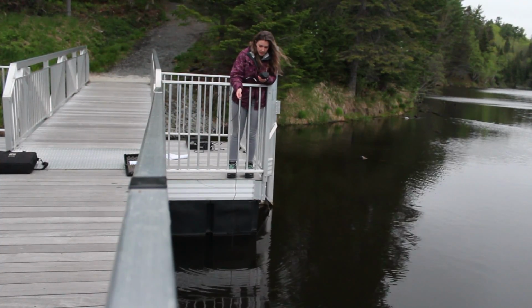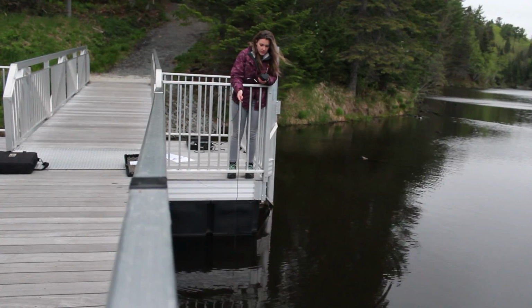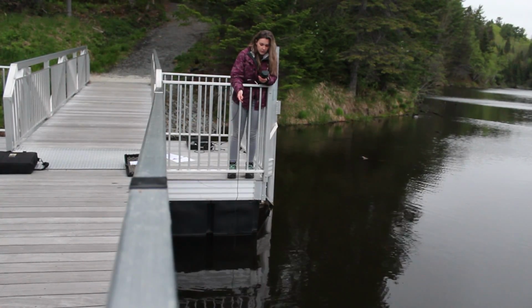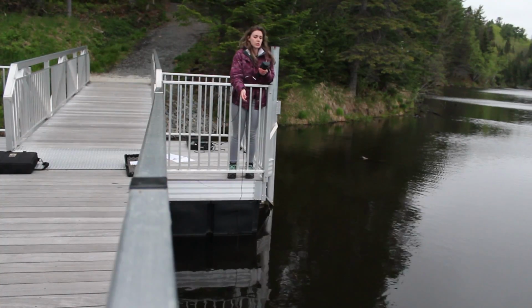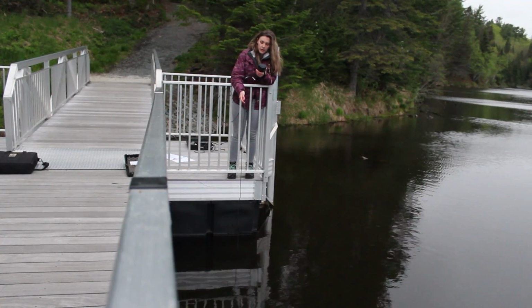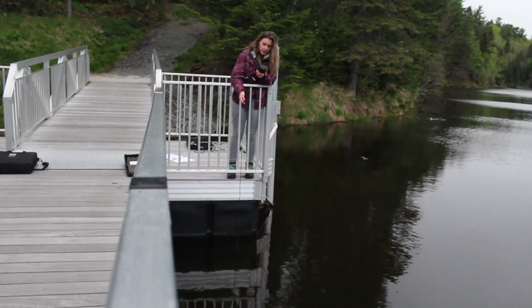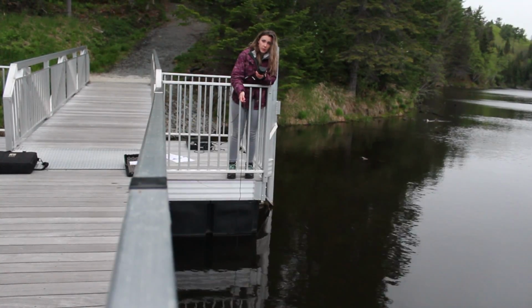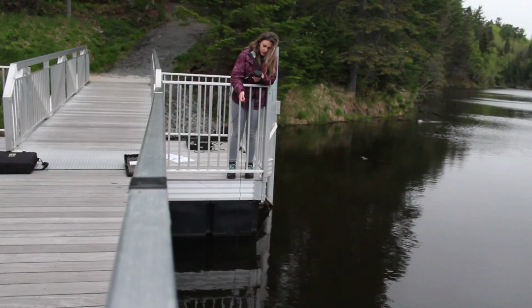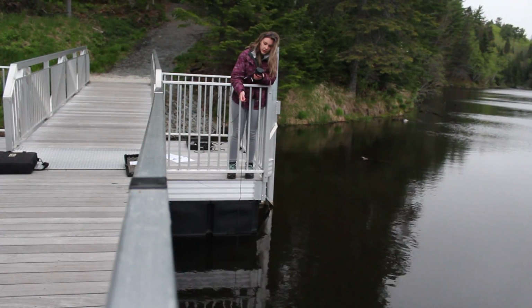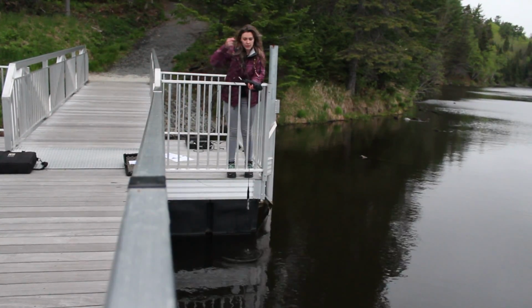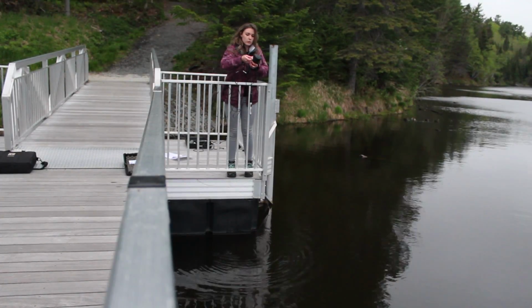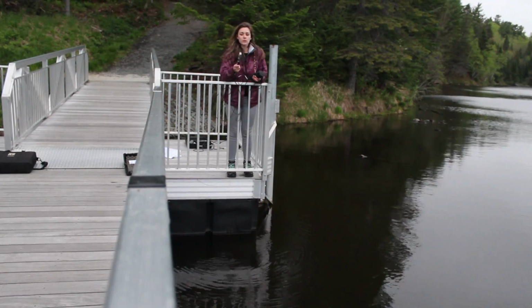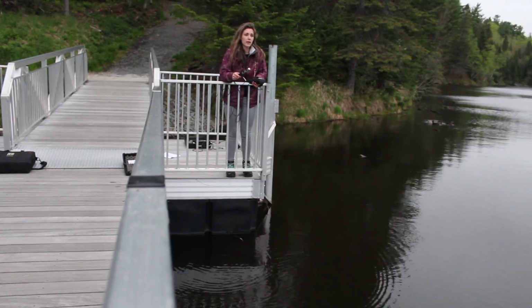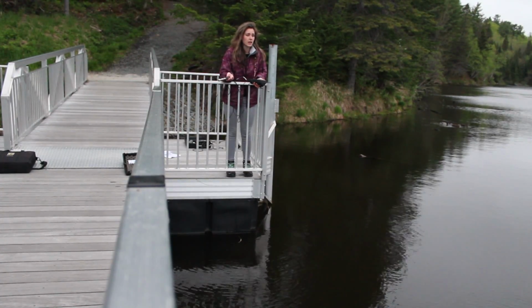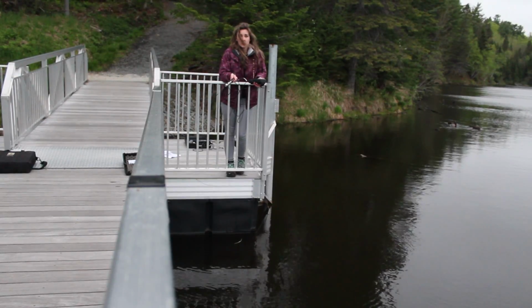Then you just wait for a minute to let it sit. And then it will give you a reading of temperature, the pressure in the water, the dissolved oxygen in milligrams per liter, and the dissolved oxygen in parts per million. And I think that you can save this one on file so that you can look at it later. For storage and everything, you should probably just clean the probe off with distilled water after you're done using it, so that you don't get any cross-contamination if you use it on a different site. Yeah, and that's pretty much it.